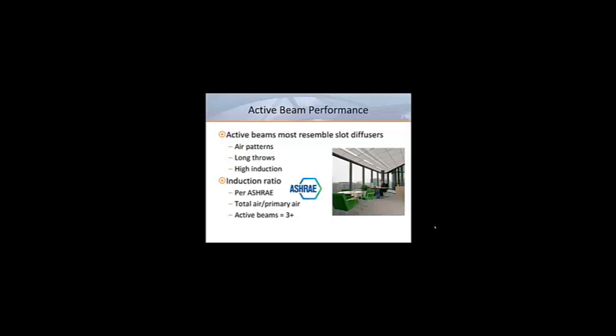When describing the air distribution characteristics of an active beam, it could be said to perform like a linear diffuser. Just like linear diffusers, active beams are commonly available in one-way and two-way models, either allowing air to move in one direction or two directions. The throw performance also resembles a slot diffuser with relatively long throws and high induction. There's that word induction again. The amount of induction created by nozzles is critical to the performance of an active beam.